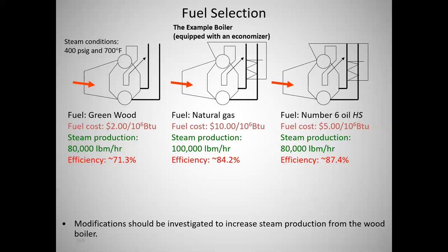You cut that valve, bingo, you've reduced the heat input rate immediately. But when you get a big mass of wood, think of a campfire. You quit throwing wood in, but you can still sit there by the campfire a long time, right? Because all that stuff is still burning. So it's not going to respond as quickly as natural gas, and the fuel oil is going to be kind of in between.